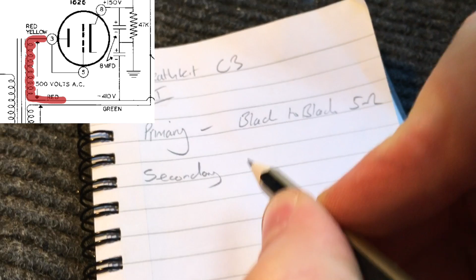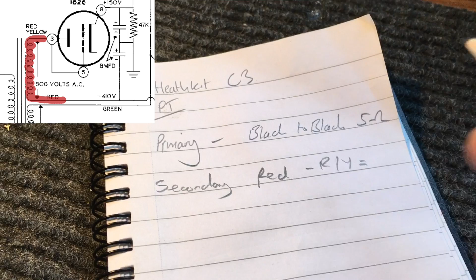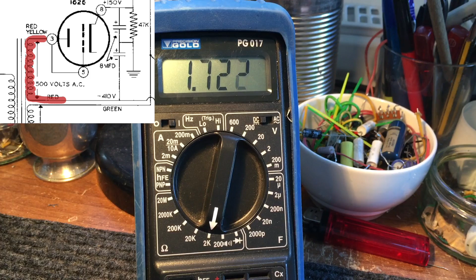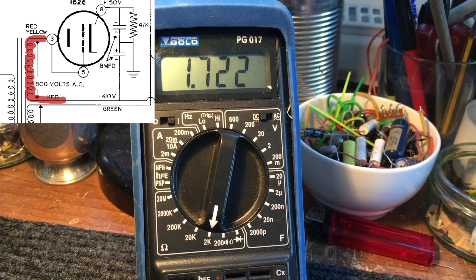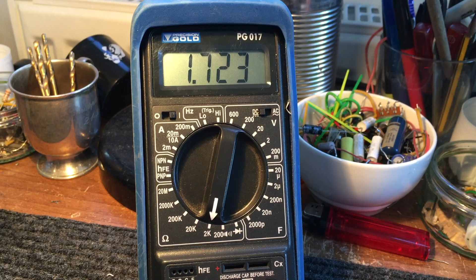So over here I just quickly wrote out primary, black to black, 5. Secondary, red to red yellow equals - so one connection there. When I'm measuring voltages later, I'll do the same connection points. So it's coming in at 1,722 ohms, 1.7k - so that's not open either. That's a good thing, excellent.